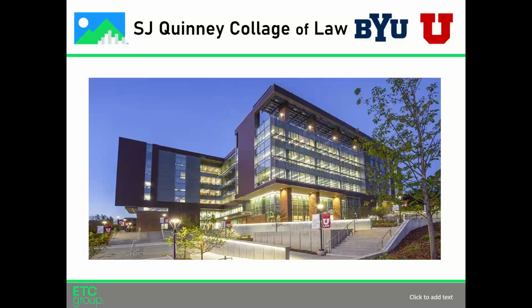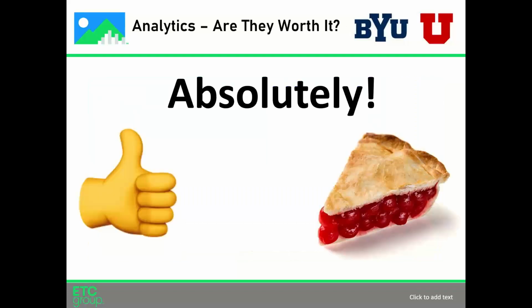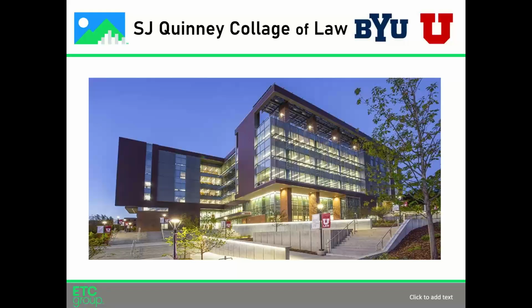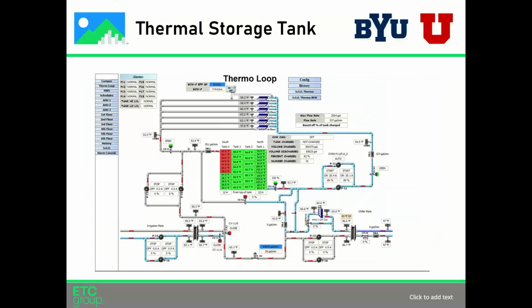I'm going to talk about our S.J. Quinney College of Law building. It's a new building, constructed and went into operation in 2015. Our cooling system is a thermal storage tank, not directly connected to a chiller. It uses a mixture of irrigation water exchanged through a flat plate, with a secondary tie-in to our chilled water plant. The challenge upon completion was that during summer months we could never recharge the tank to full capacity during off-peak hours, which ultimately led to customers being uncomfortable.